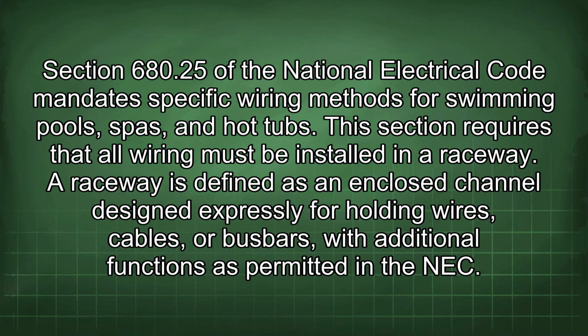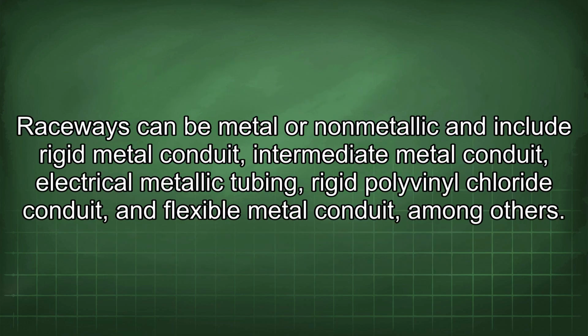680.25 of the National Electrical Code mandates specific wiring methods for swimming pools, spas, and hot tubs. This section requires that all wiring must be installed in a raceway. A raceway is defined as an enclosed channel designed expressly for holding wires, cables, or busbars, with additional functions as permitted in the NEC. Raceways can be metal or non-metallic and include rigid metal conduit, intermediate metal conduit, electrical metallic tubing, rigid polyvinyl chloride conduit, and flexible metal conduit, among others.